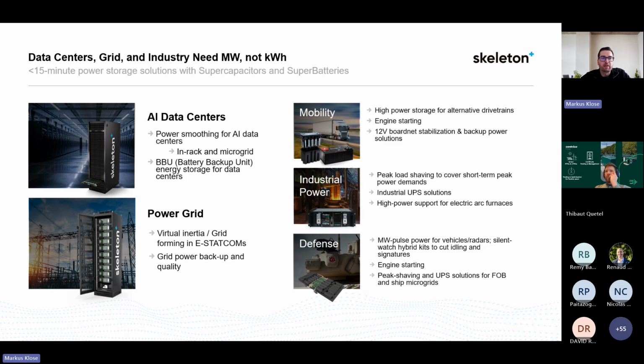Independently of AI data centers, you can also stabilize the grid with virtual inertia grid and e-StatComs. It's a very big topic in Europe, especially since the increase of decentralized energy and power generation and the loss of inertia in the system. You have fewer turbines connected to the grid that can compensate for that, so you have to compensate power fluctuations and spikes in a different way.